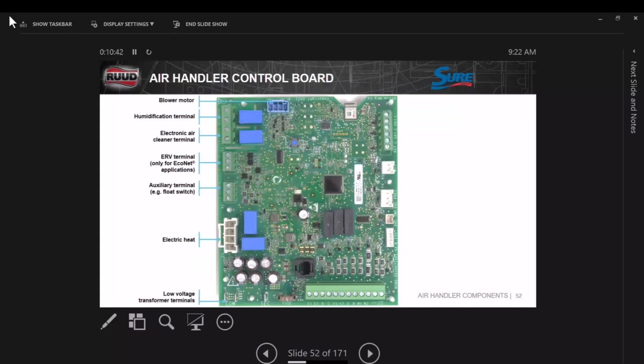Hey, it's basically the same. You see the terminals here. You have the humidification terminal up there for it too. You have a terminal for the electronic air cleaner on the air handler board. You do have a place for the ERV. If your unit was an ERV, this is the same control that we would use. Float switch, just like we talked about on the gas furnace.